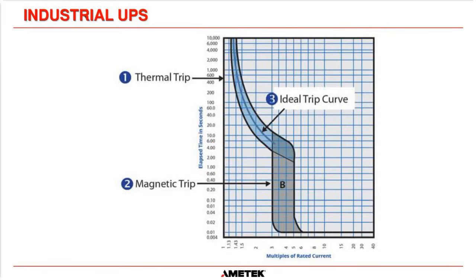But with the 120 volt UPS, you have 8.3 times the current. Actually, if it's a 10 amp breaker, you can have 83 amps, but let's say the UPS is loaded at half the load. So you only have 40 amps available. That's still 4 times the 10 amp rating of the breaker, and therefore the breaker is going to trip in 0.01 seconds, near enough instantaneous. So you can see how much better a single phase UPS clears faults on the output of the system.